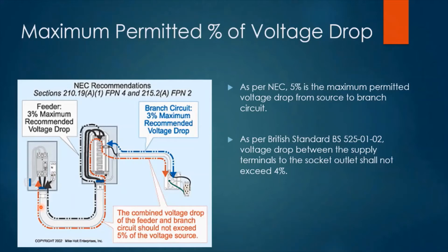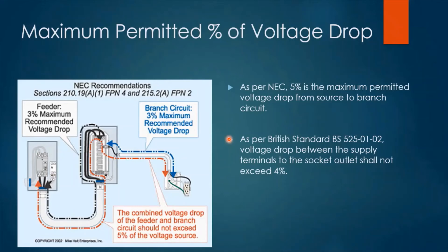According to the National Electric Code (NEC), 5% is the maximum permitted voltage drop from source to branch circuit. As clarified in this diagram, a 3% maximum voltage drop from the MDB or main DB to SMDB is recommended, and similarly 3% is permitted from the ADB to a branch circuit. It is also stated that 5% is the maximum permitted voltage drop combining the feeder and the branch circuit. According to British Standard, a maximum voltage drop of 4% is permitted between the supply terminals and the socket outlet. This means we consider 4 to 5% maximum voltage drop in our design calculations.